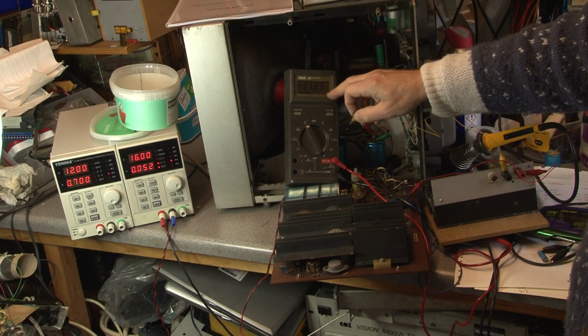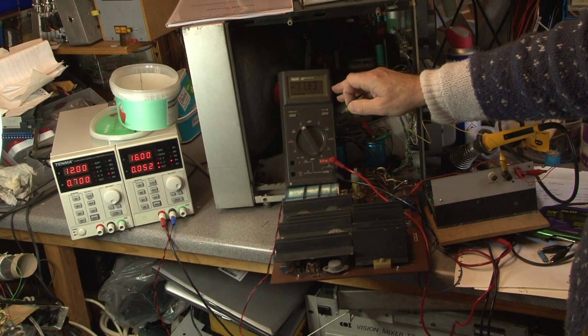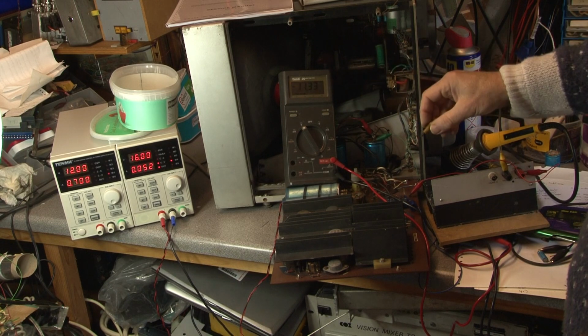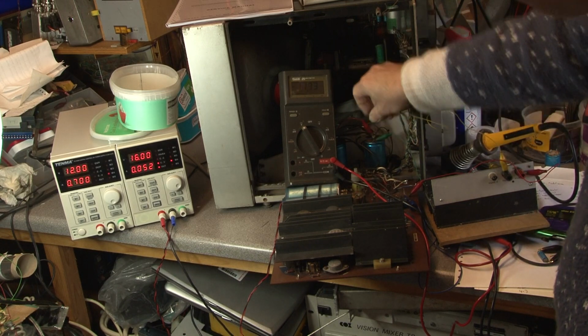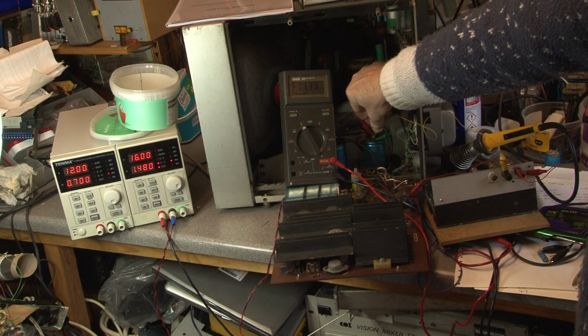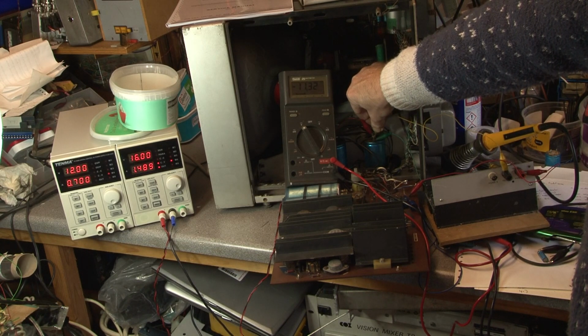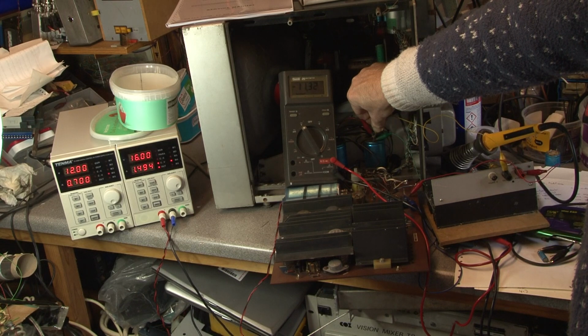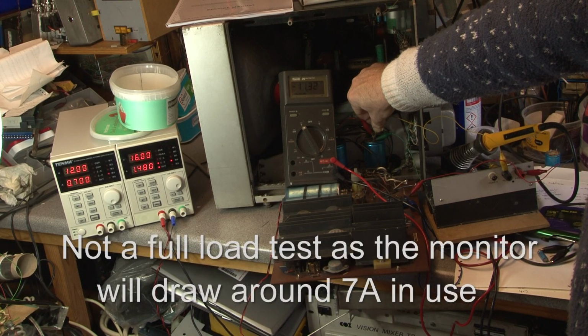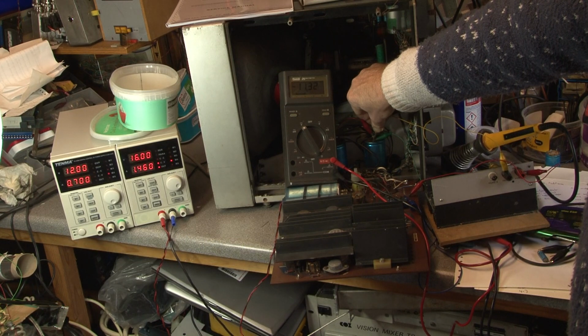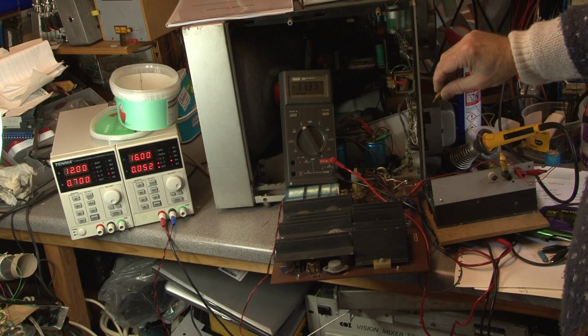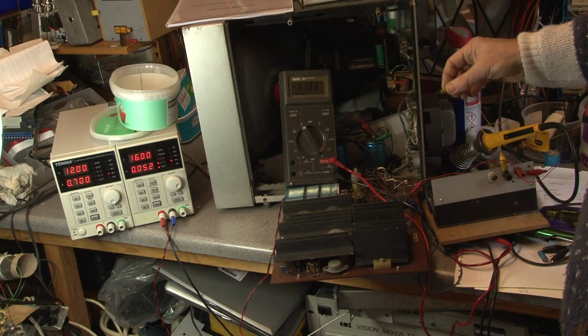The important thing to do is to have a look at the voltage to see if that is being regulated. So I'll just put the ground on and we'll see. The power supply is showing now just under 1.5 amps, as I would expect, and to our relief the regulator is still producing minus 11 and a bit volts, so that's hardly changed between a reasonable load and no load. That's pretty good.